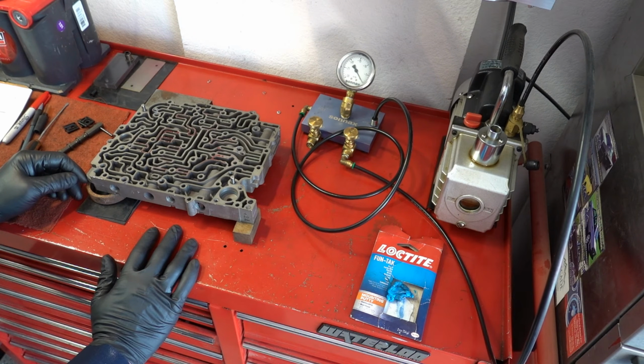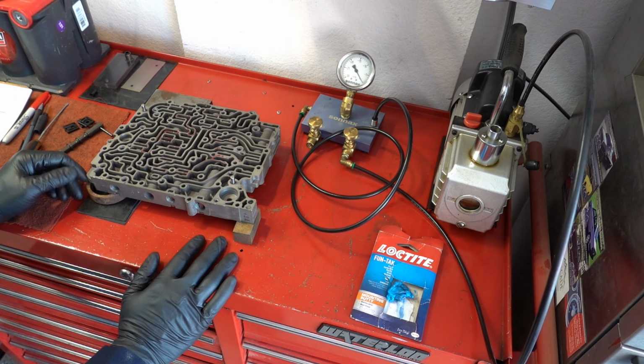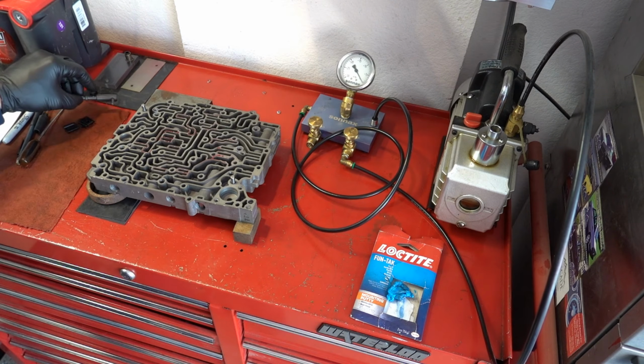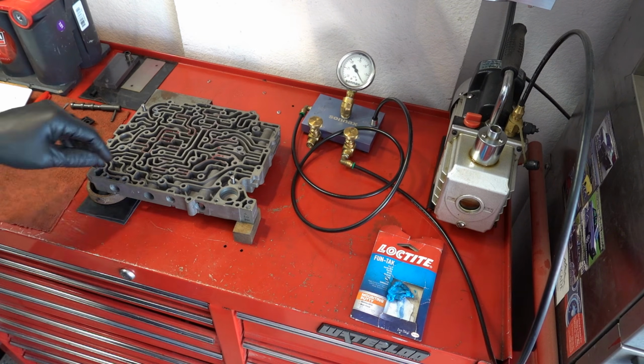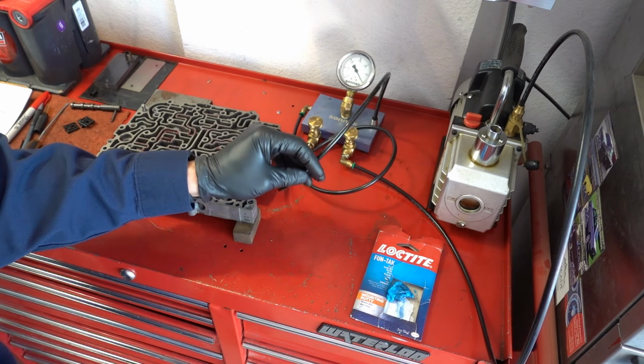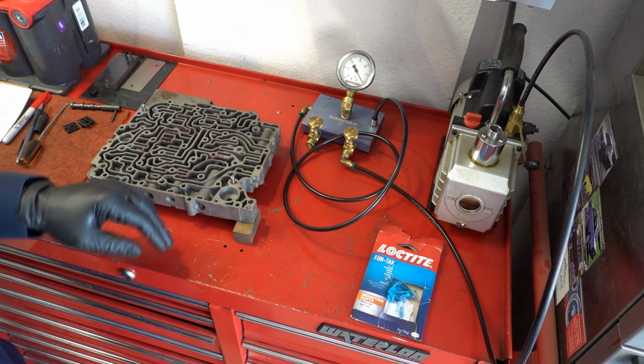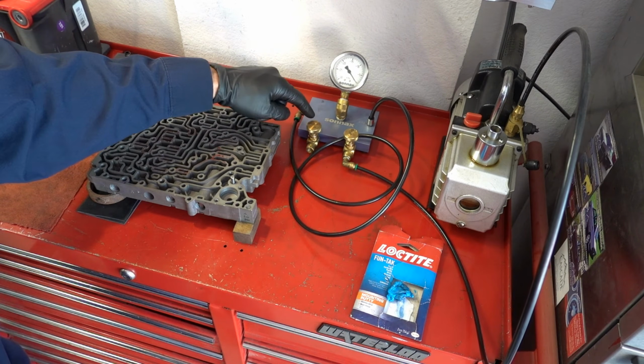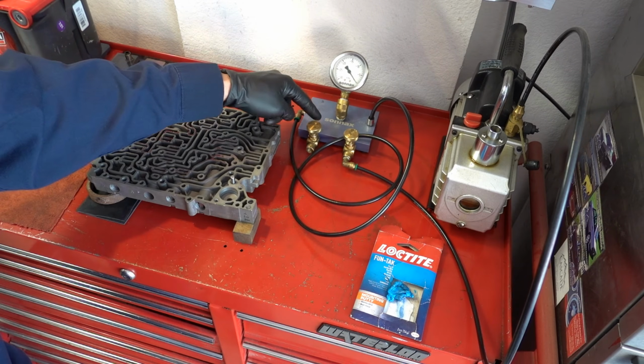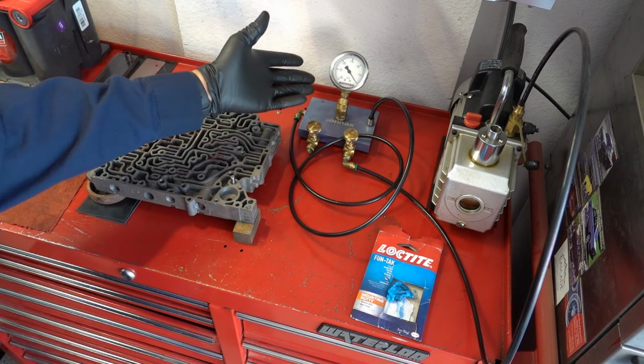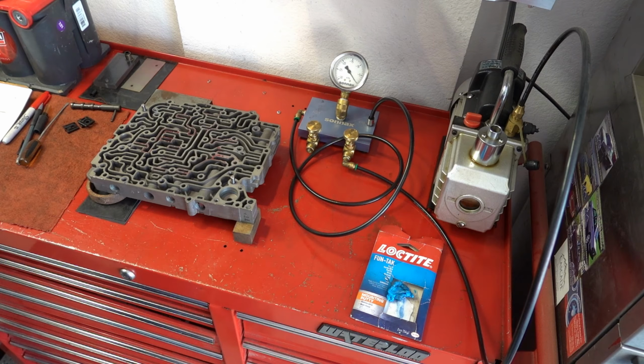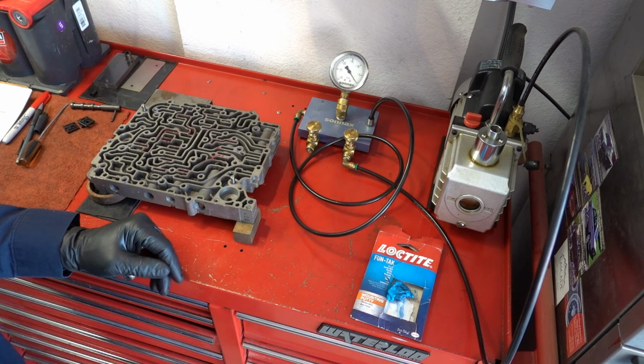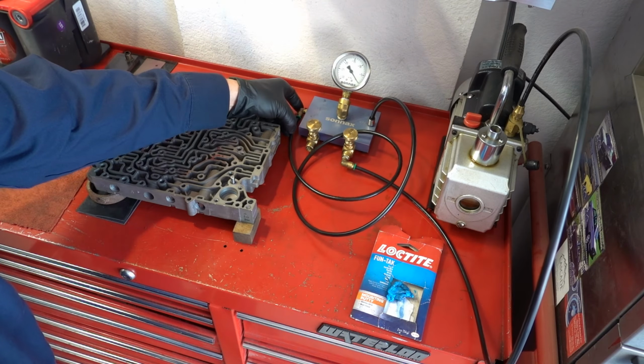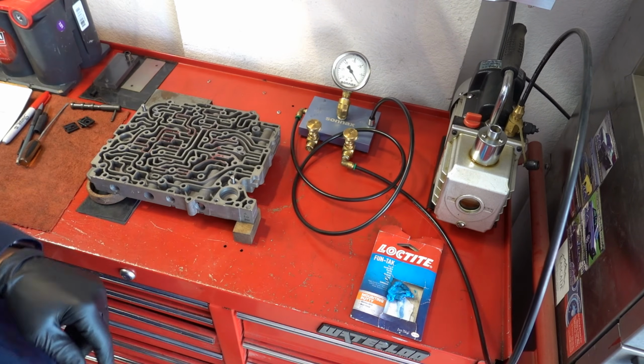Like any vacuum test, the first thing you have to do with the machine is calibrate it before you can use it. Otherwise you're at risk of generating invalid results. For the Sonics machine, they have a calibration receptacle, and you're going to take your test lead and insert it into that receptacle. You have your gauge, obviously, and then you have 2 valves, a bleeder valve and a pump valve. The pump valve has a hose that goes into the air pump, and the air pump doesn't come with the machine, at least not from Sonics. You can go to any hardware store or online and pick one up. Then you have your test lead, which is what is being inserted into the calibration receptacle.